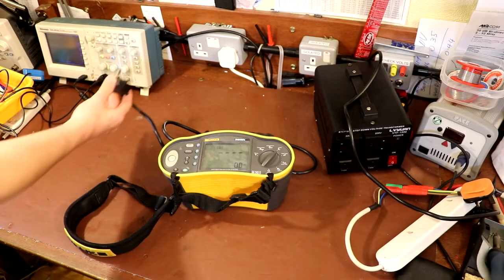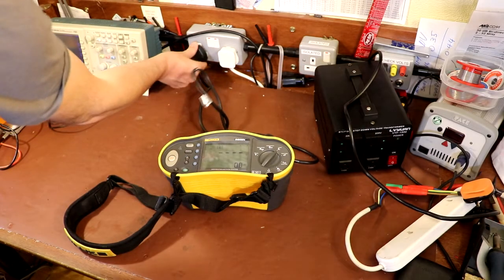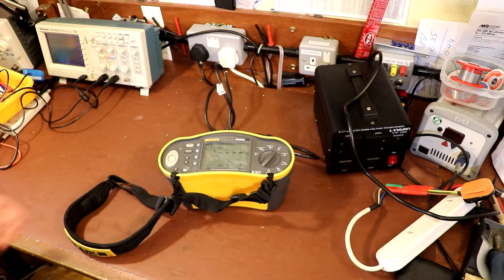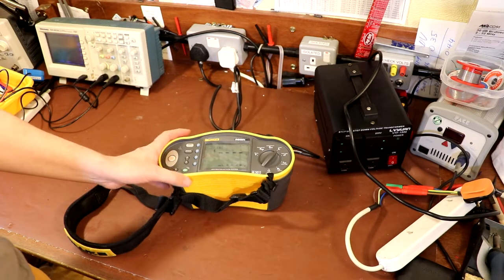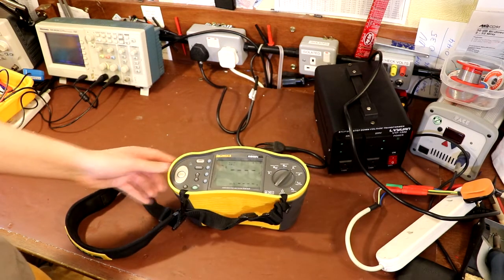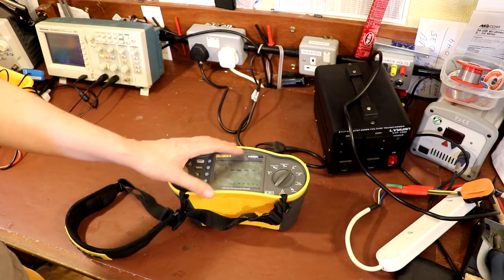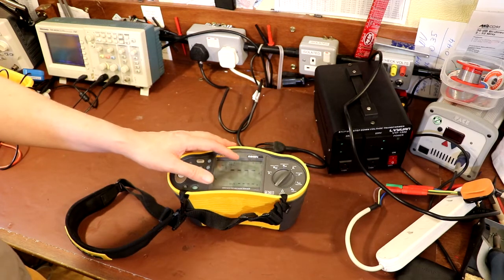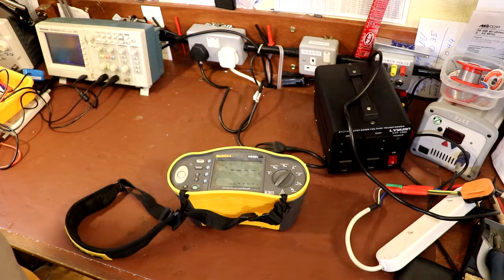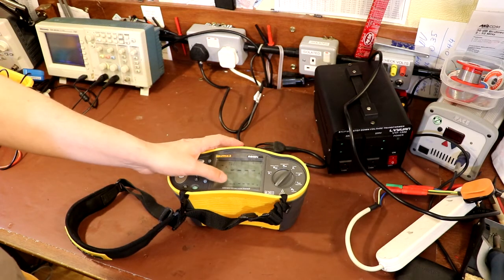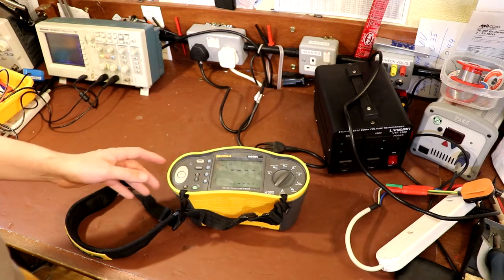So I'm going to plug our tester into the same socket that's been supplying our transformer all the time, and all we're going to do is press the test button. It takes a few seconds to do the test, and it's going to give us the loop impedance, the resistance of our conductors here, and it's also going to give us something called the PFC, which is the prospective fault current.